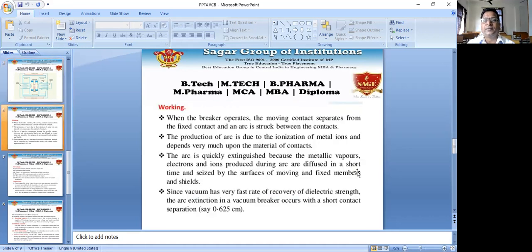Working: when the breaker operates, the moving contact separates from the fixed contact and an arc is struck between the contacts. The production of the arc is due to the ionization of the metal vapors and depends very much upon the materials of the contact. The arc is quickly extinguished because the metallic vapor, electrons and ions produced during the arc are diffused in a short time and seized by the surface of the moving and fixed members and shields. Since vacuum has a very fast rate of recovery of dielectric strength, arc extinction in a vacuum breaker occurs with a short contact separation, say 0.625 centimeters.